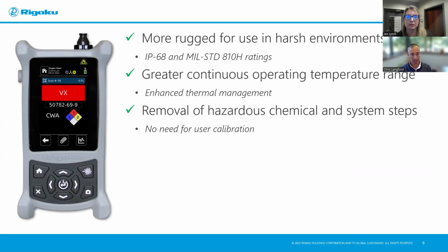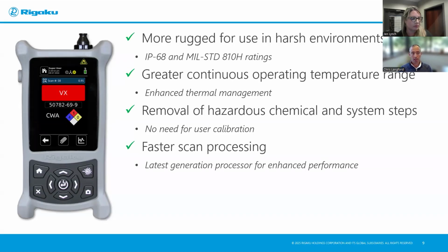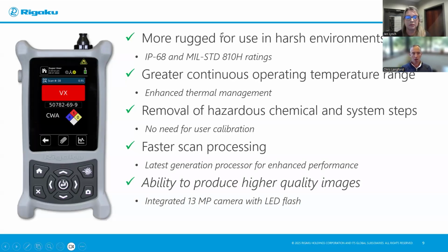We've been able to eliminate the need to calibrate the device, which removes both a process step as well as the need to have the benzonitrile calibration standard in the kit. With the latest and available high-tech processors embedded in the system, this yields faster scan times. Specifically, once the data is collected and passes into the algorithm space for processing, you will notice the instrument works faster. We've also embedded the latest tech with regards to cameras. So we have a nice 13 megapixel camera for just better quality image capturing.